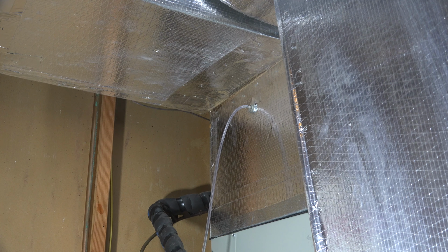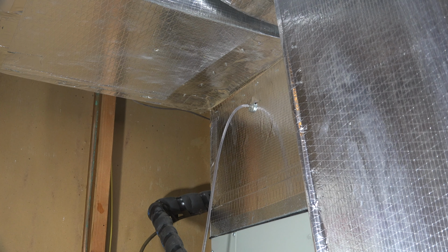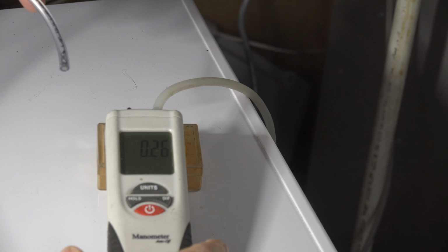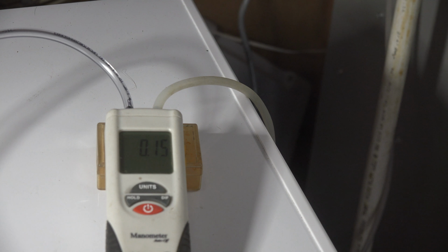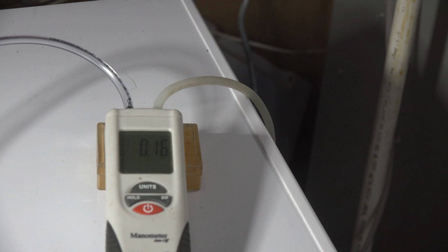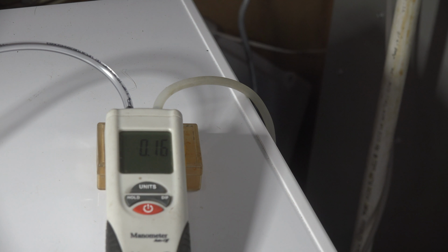Okay, there you can see that second probe. Now when I plug in the hose from that second probe, there's going to be a change in the pressure read, and it's just going to read the pressure difference across this coil. Okay, it's showing 0.26. Now, with that hose hooked up, we're now sitting at 0.16. So what we've got is a pressure drop across the coil, 0.16. Now that's well within specs. I'll accept 2/10 of an inch, sometimes 3/10 of an inch across these things, depending on fan speed and coil size. But 2 or 3/10 is probably fine.